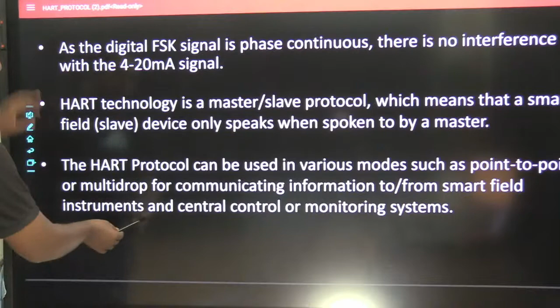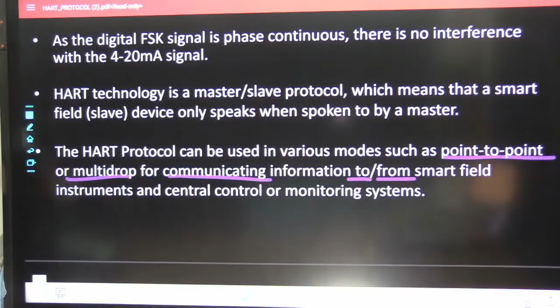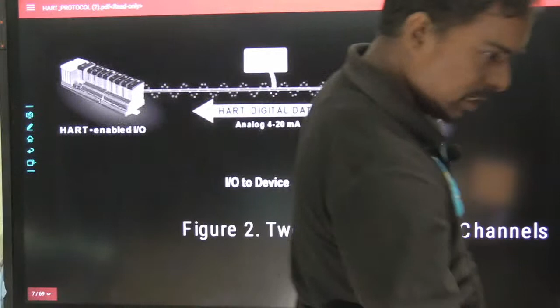Multiple slaves can be connected to the HART controller. The HART protocol can be used in various modes such as point to point. See, this is also important. It can be used as point to point or multi-drop for communicating information to and from smart field devices. It can be point to point, it can be multi-drop also. I will show you the pictures. See here. If you see this device, I think you are able to see this picture clearly.